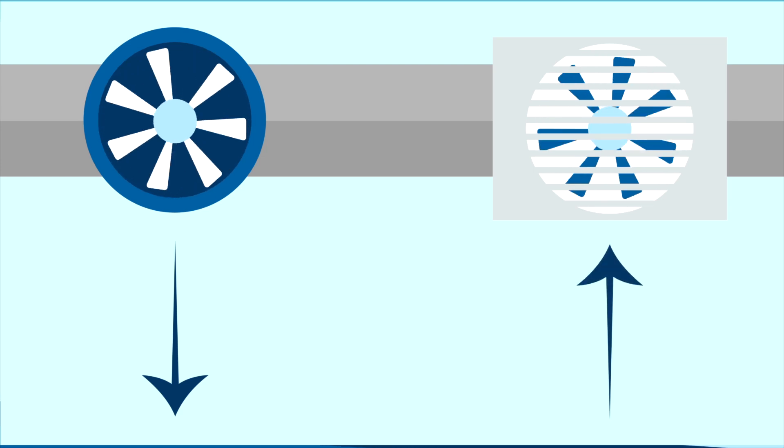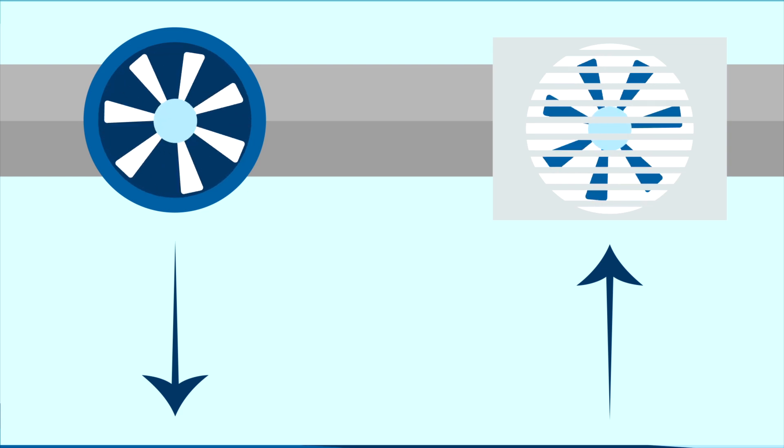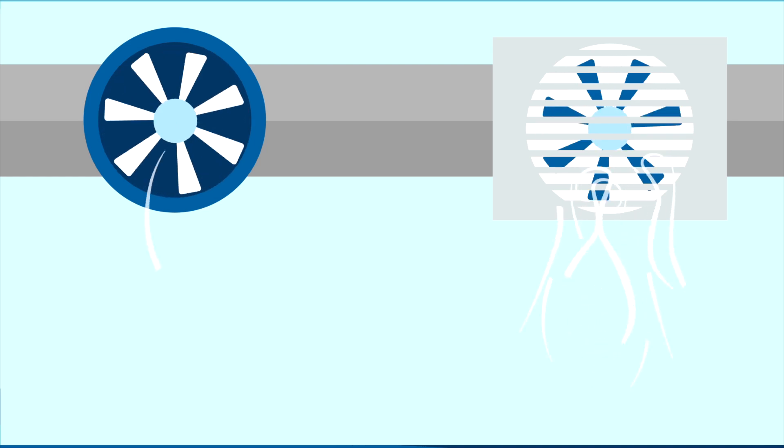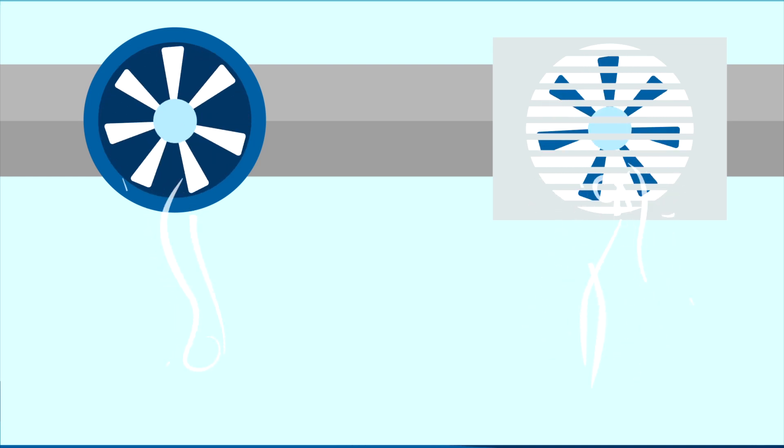Whichever fan is doing more work determines if the room is positive or negative pressure. Negative pressure means the exhaust fan is pulling more air out of the room than the supply is pushing into the room.